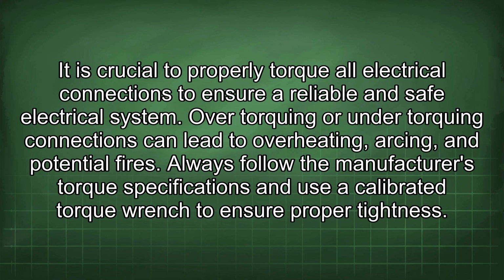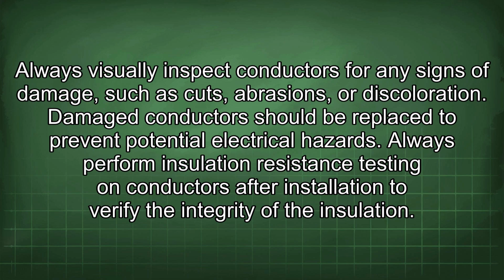It is crucial to properly torque all electrical connections to ensure a reliable and safe electrical system. Over-torquing or under-torquing connections can lead to overheating, arcing, and potential fires. Always follow the manufacturer's torque specifications and use a calibrated torque wrench to ensure proper tightness. Always visually inspect conductors for any signs of damage such as cuts, abrasions, or discoloration.